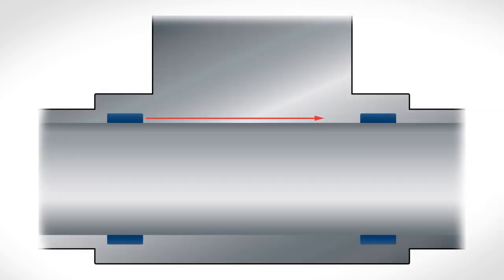Part of the wave travels directly to the first receiver along the surface of the tube, and part of the same signal is transmitted through the fluid to the opposite side of the tube where it splits again, with a proportion going to the second receiver and the remainder traveling back through the fluid where the process repeats itself.